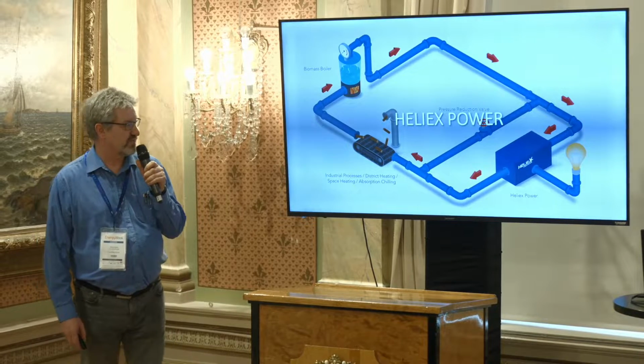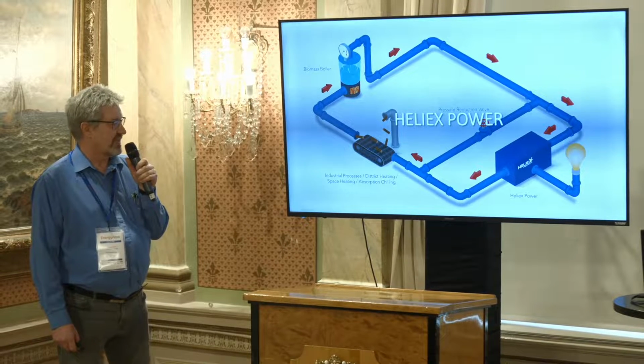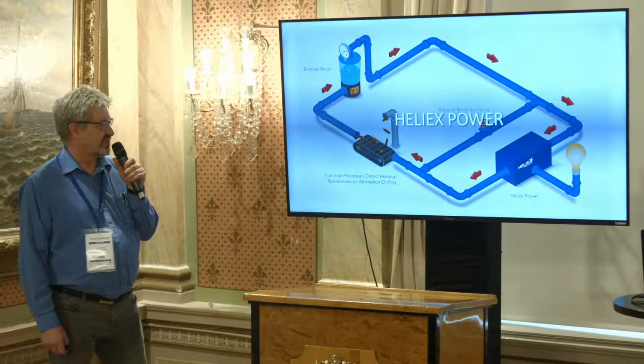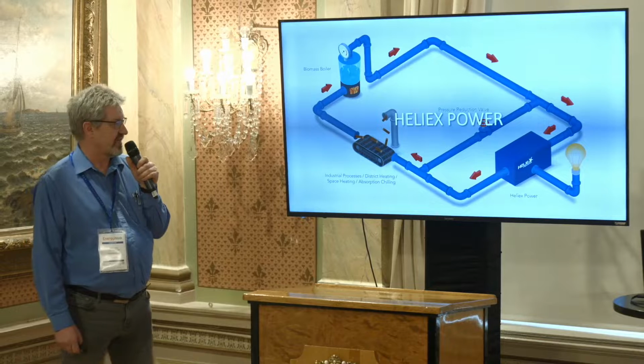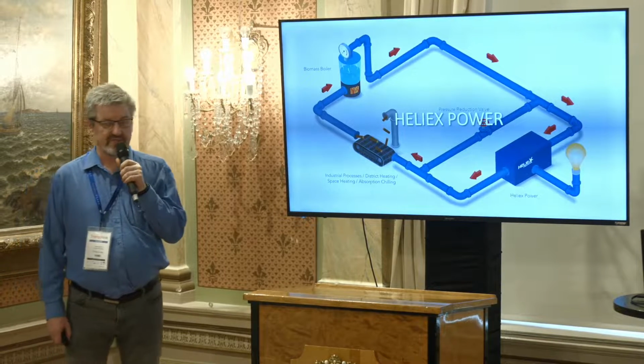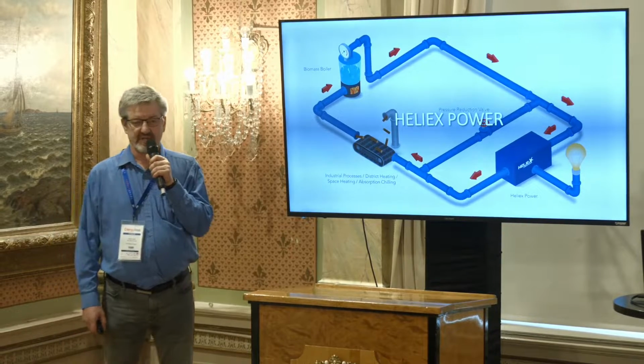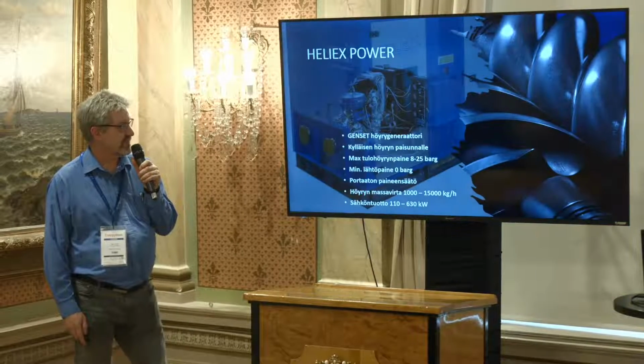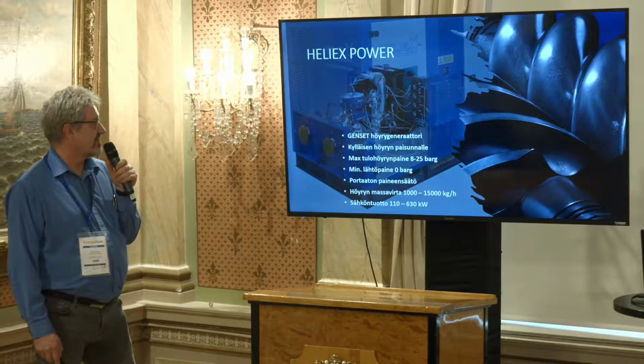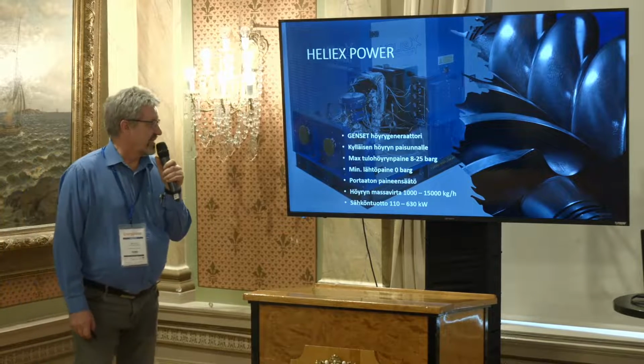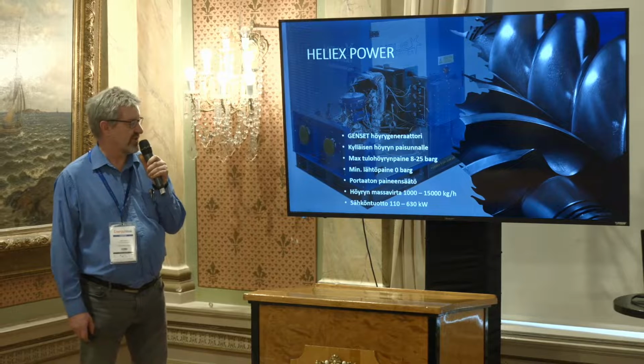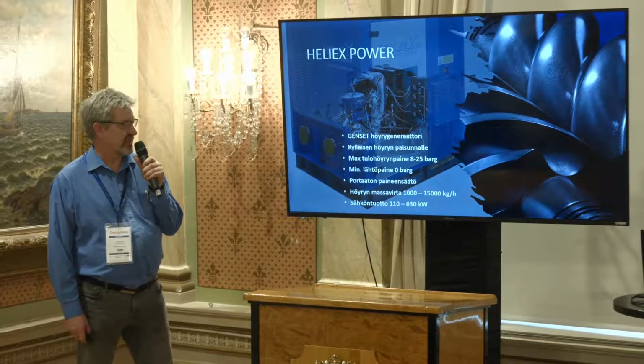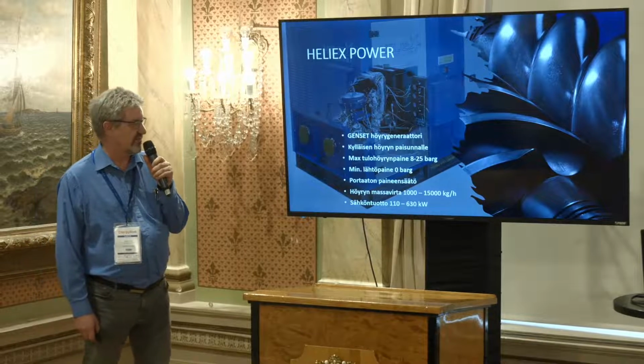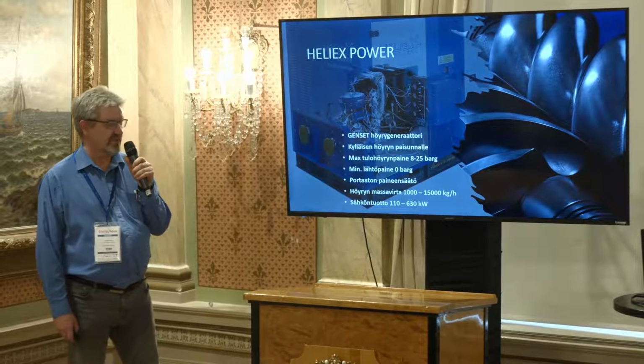This is the principle of how to use that Heliex generator. It can be installed on the side of a reduction valve. So in that reduction valve technology, we lose the energy we have at the pressure drop point. With Heliex, we can take that energy into use. The generator is capable of using saturated steam. Maximum input pressure is 25 bar and output minimum is 0 bar.